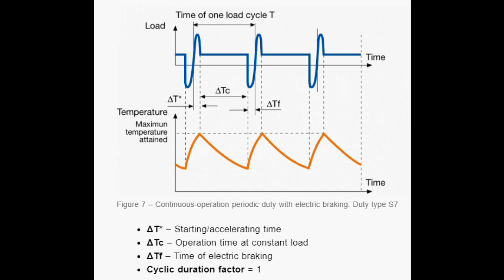At S7, we have a starting time, a time of operation at constant load, and a time of electric braking. We do not have any time de-energized and at rest. The machine starts, runs at constant load, electrical braking occurs, and just after that, again it is started.